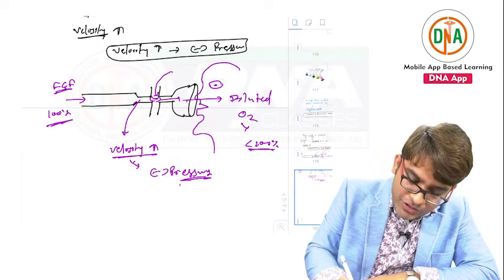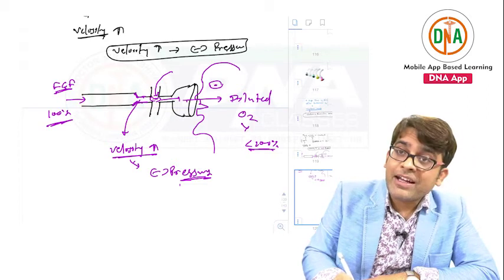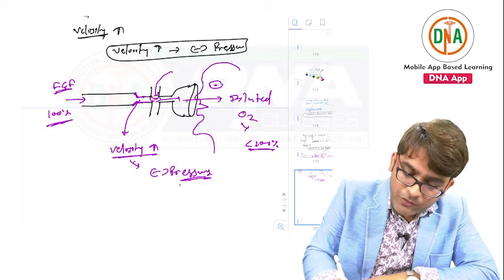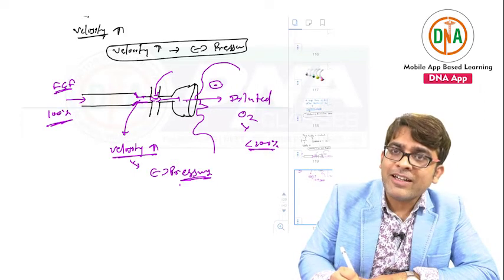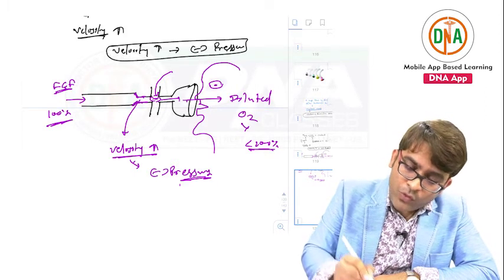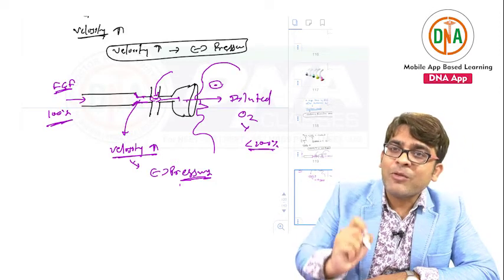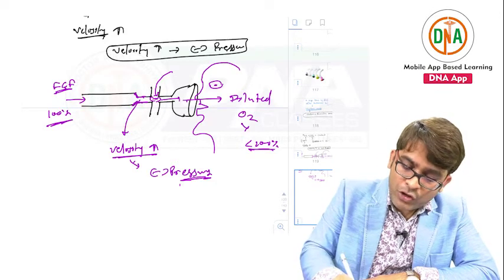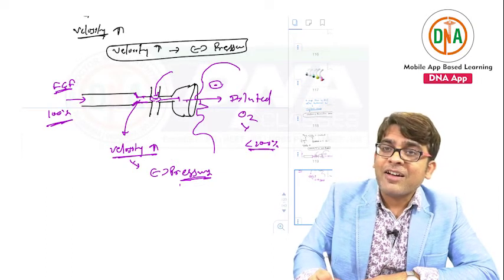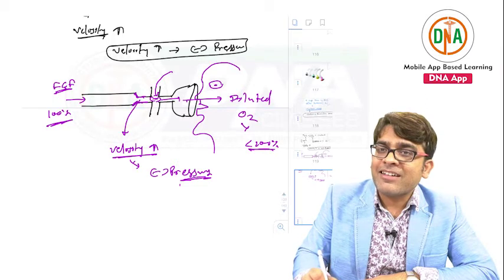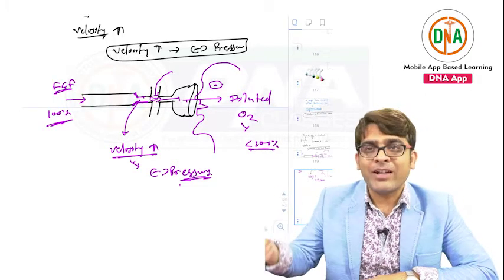Actually, this constriction is fixed. When this constriction is fixed, the air entering from the atmosphere into this mask will be fixed. Okay, so in fixed flow, fixed constriction, fixed dilution will occur. Getting my point? And the FiO2 the patient gets will also be fixed.